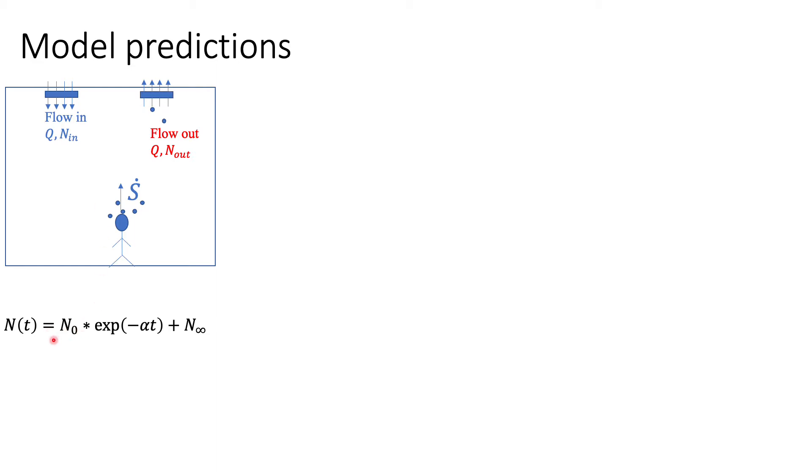The expression for particle concentration change over time remains the same, but these constants now have simpler expressions. Alpha is the ratio of the flow rate coming in divided by the volume, and we call that the air changes per hour. If the flow rate you bring in one hour equals the volume of the room, your air changes per hour would be one. Bring in more flow, you've got higher air changes.